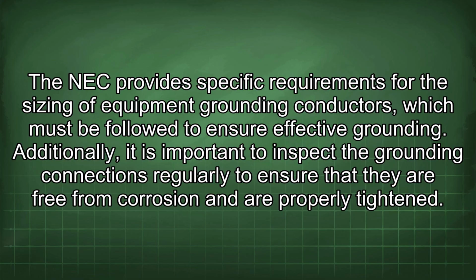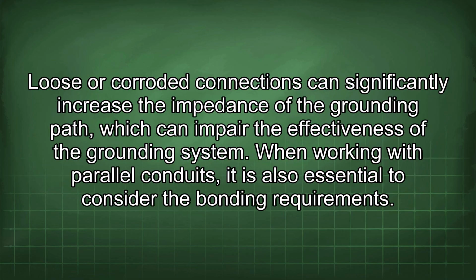Additionally, it is important to inspect the grounding connections regularly to ensure that they are free from corrosion and are properly tightened. Loose or corroded connections can significantly increase the impedance of the grounding path, which can impair the effectiveness of the grounding system. When working with parallel conduits, it is also essential to consider the bonding requirements.